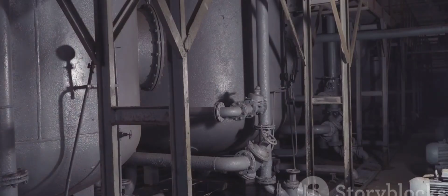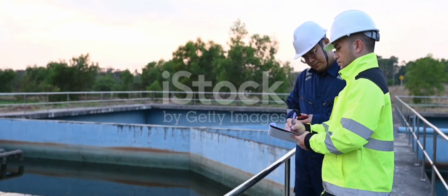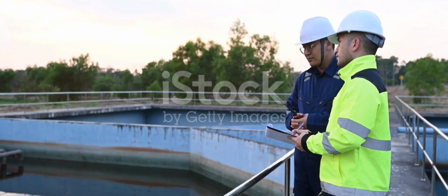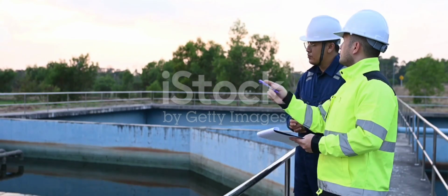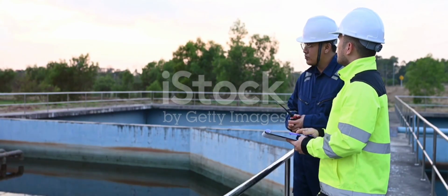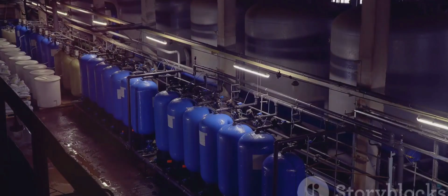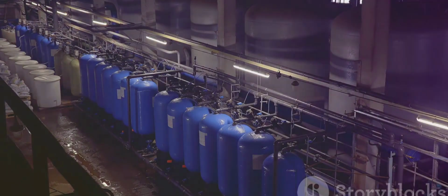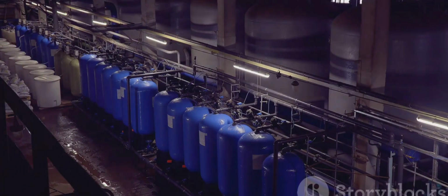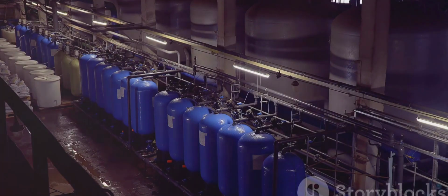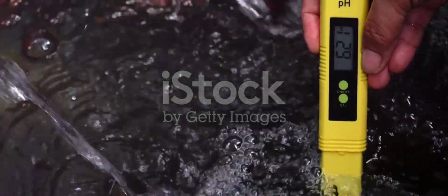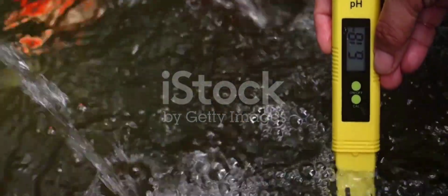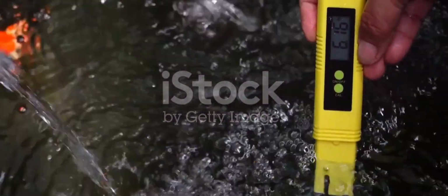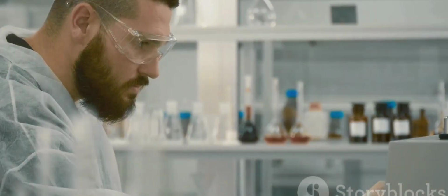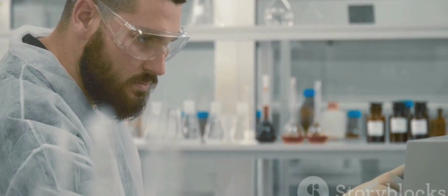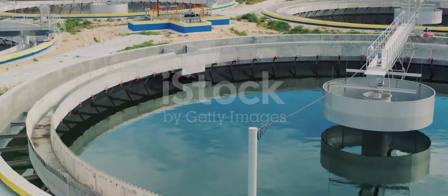pH adjustment. The pH of the treated water is adjusted to ensure it is within the desired range, especially for specific industrial processes. Acids or bases, such as sodium hydroxide or sulfuric acid, are added to achieve the required pH balance. Key parameters to watch include the pH value, which is typically between 6.5 and 8.5, and the acid or base dosage, measured in milligrams per liter.